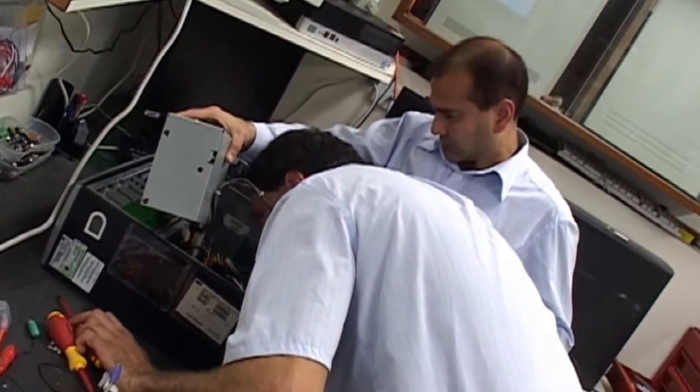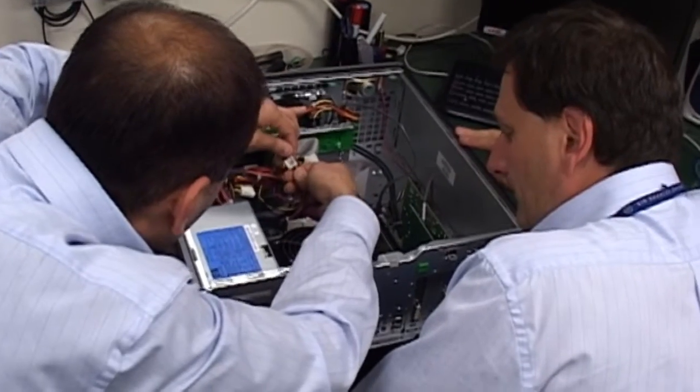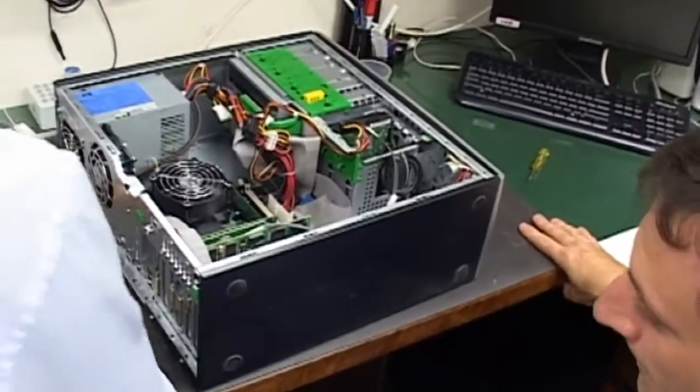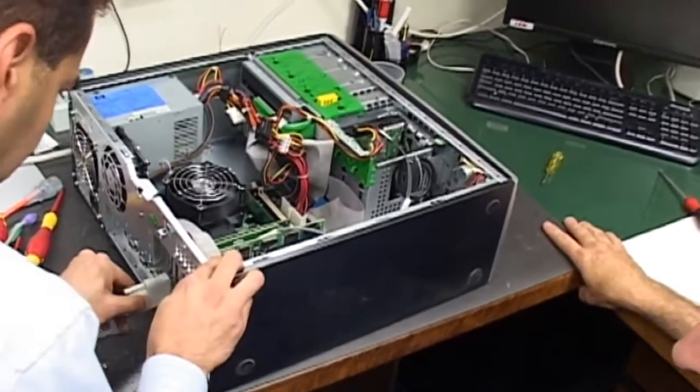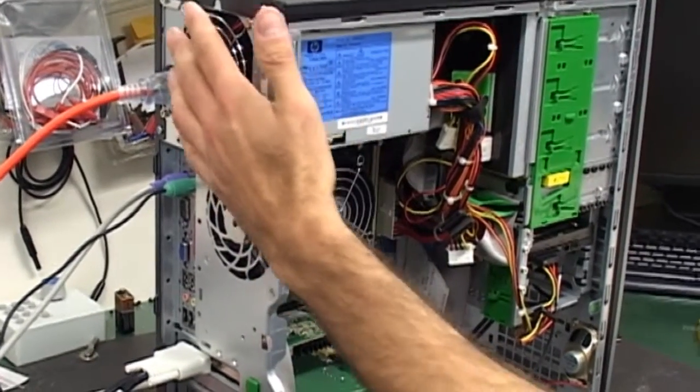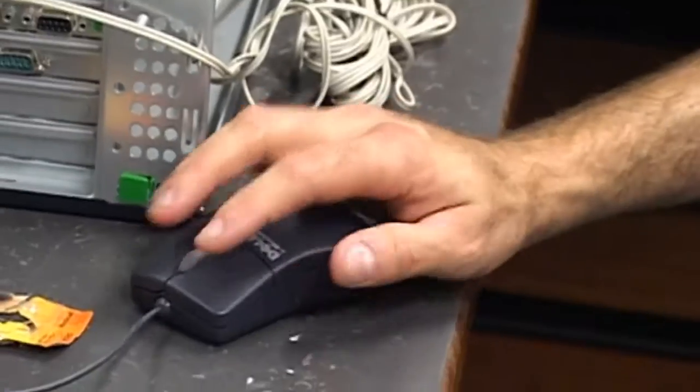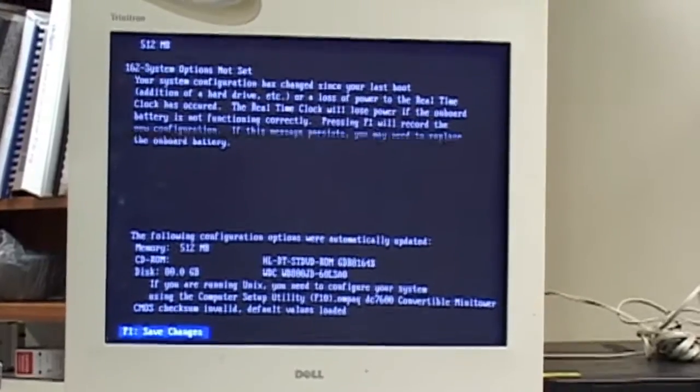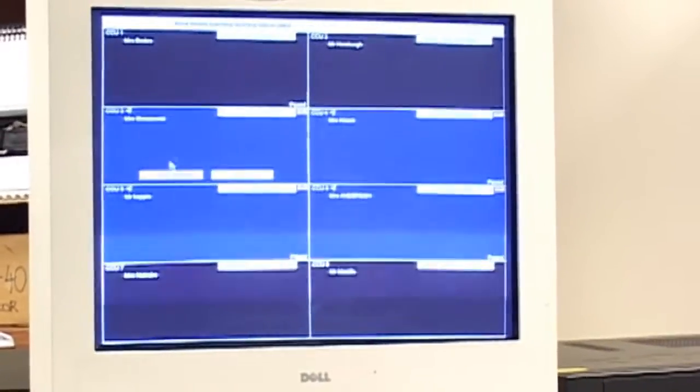As far as central stations go and patient monitoring, that's where the IT component is. So if something happens to it, if it crashes or glitches for whatever reason, to understand the computer basics behind it, how to resolve that. Does it need your standard restart? Has a hardware failed on the computer? Was it just a glitch where a reboot is more than enough?